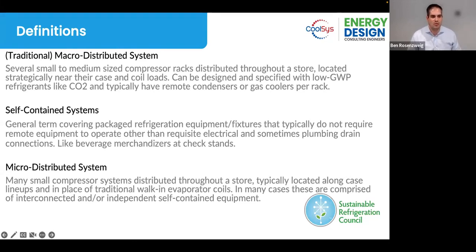This type of system is one where you might have several small to medium sized compressor racks with multiple compressors, kind of like a traditional central refrigeration rack, throughout a retail store located strategically near case and coil loads. These are typically used to reduce refrigerant charge, potentially increase energy efficiency and compressor selections, as well as reduce piping in the store, etc.